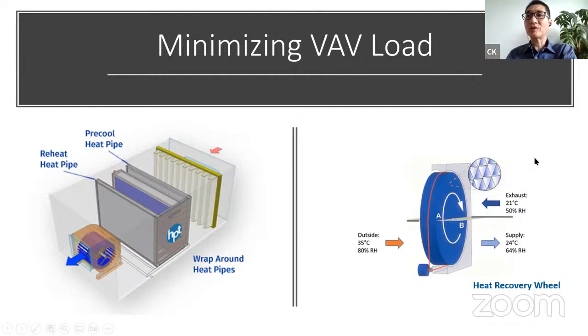In addition, we put in a heat recovery wheel for the fresh air, because we have a lot of fresh air coming in. We put in a very high efficiency heat recovery wheel to pre-cool and pre-dry the fresh air coming in, again reducing the load that goes to the VAV system. The more we reduce the load on the VAV system, the more efficient the entire system will be. So that's how we optimize the energy of the system.